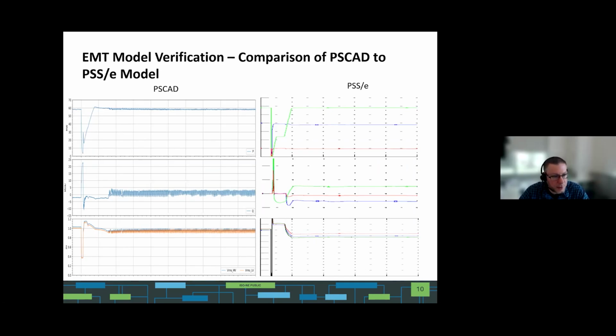On the left, you see some results from PSCAD testing. We can see the active power here does not really match the green trace on the right. And the megavars, you have the spike, but there's a bit of a drop. So generally, it's not matching. You also see oscillations in the PSCAD model that aren't in the PSSE model, which is just flat.